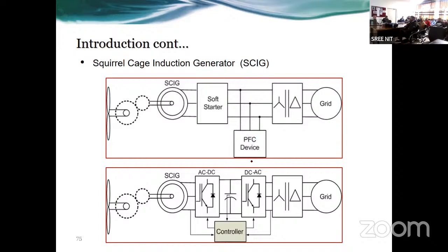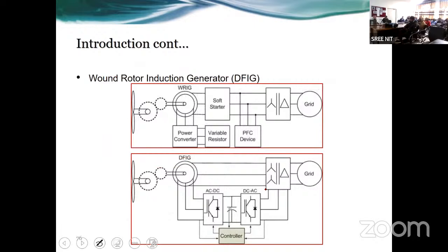But the controller which we are talking about is going to be a bidirectional back-to-back converter topology, which I am going to discuss. So PMSG based. This is a DFIG configuration, where partial power can flow through the stator and the remaining power can flow through the rotor. So rotor and stator both have power flow. Normally the rotor converter is designed for 30 to 40% of the rated capacity, while 60 to 70% of the power flows from the stator.